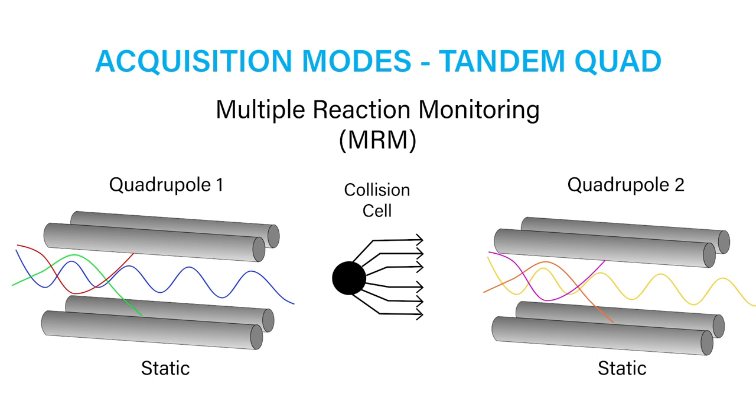This is the most common way to use a tandem quad because it is the most sensitive mode for quantitative analysis. The first quadrupole will pass only the precursor or intact form of the analyte, while the second quadrupole is set to pass a specific fragment of the analyte that was generated in the collision cell.